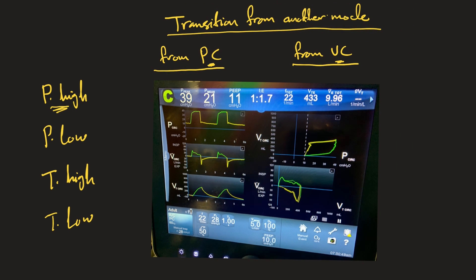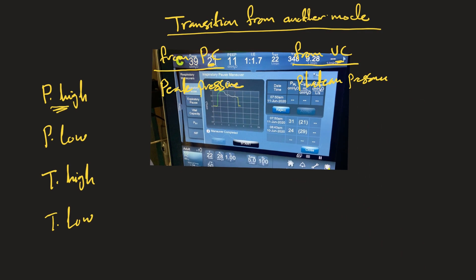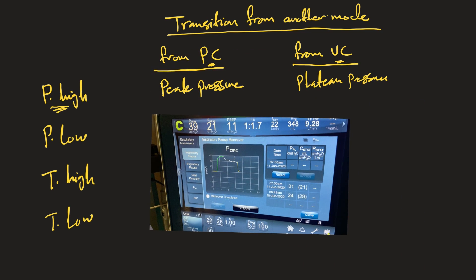For transitioning from pressure control, simply look at the peak pressure of the patient before transition. For example, if the peak pressure is 39 cmH2O, that becomes your P-high once you transition to TCAV. So in pressure control, P-high equals the peak pressure.